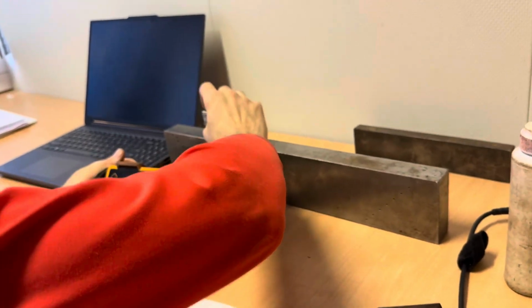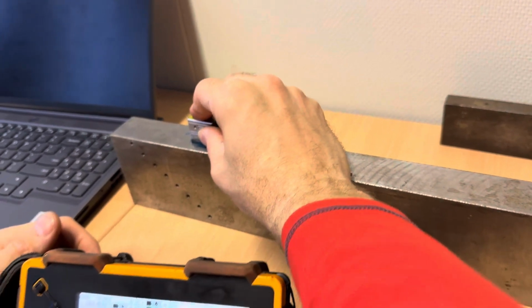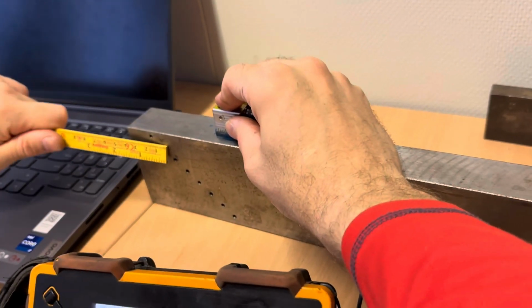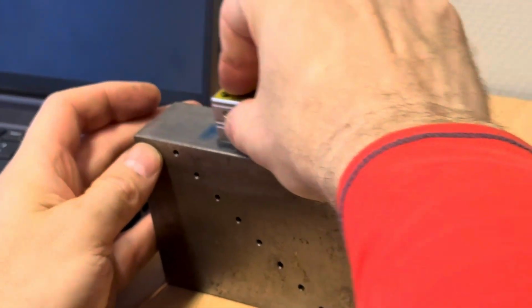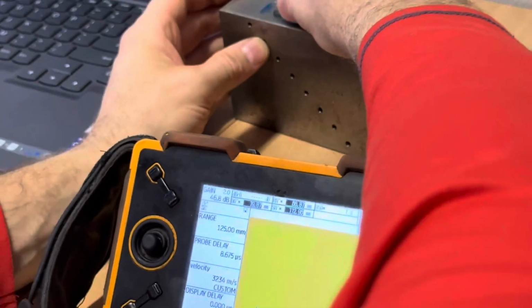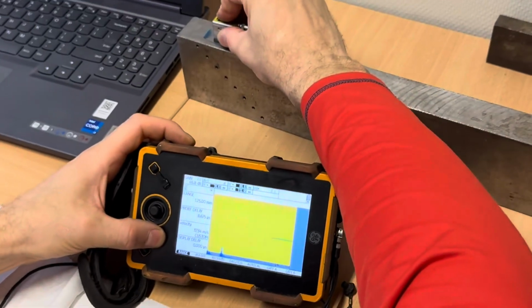We take the main calibrator, which we will use for calibration, with holes of 3 millimeters, like this, up to 3 millimeters. And we can clearly see a significant defect here. We often find some kind of noticeable defect. In decibels, up to 80 on the monitor.